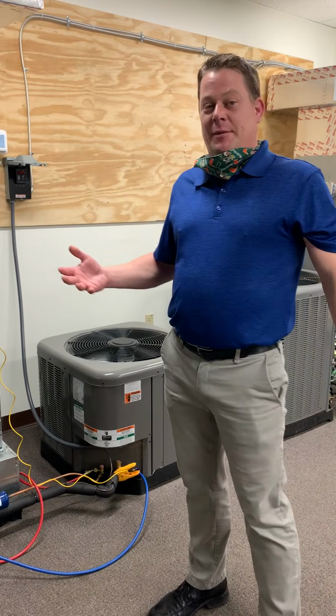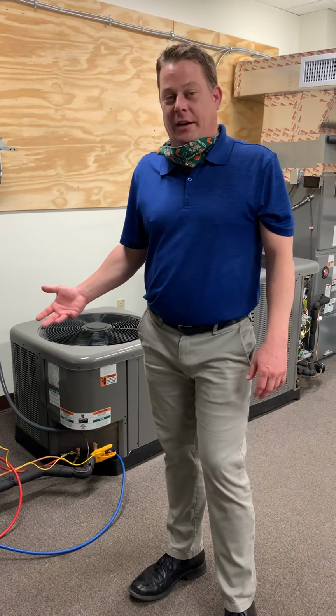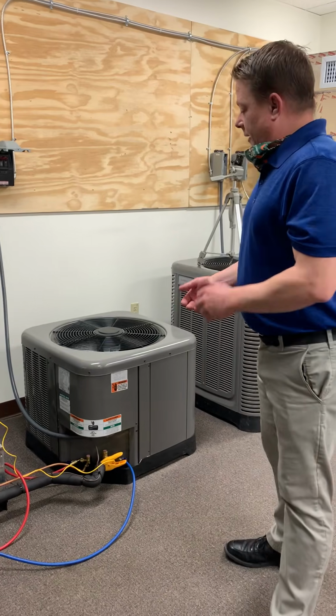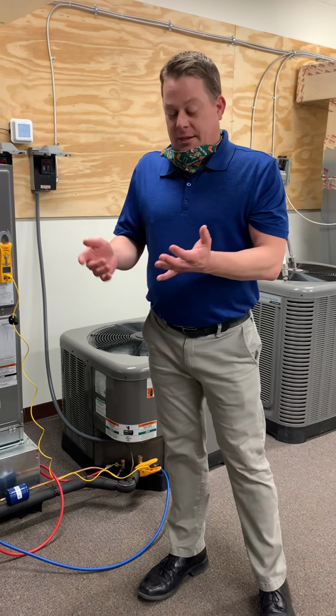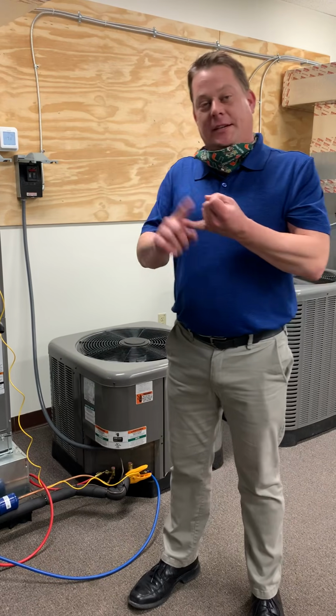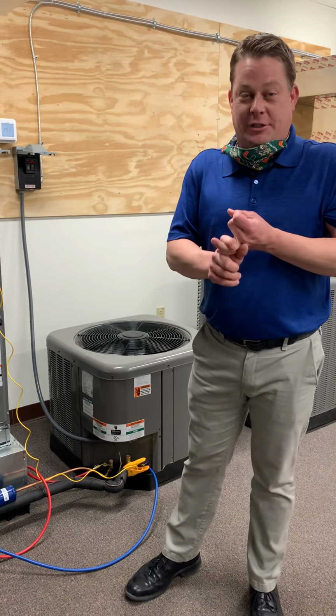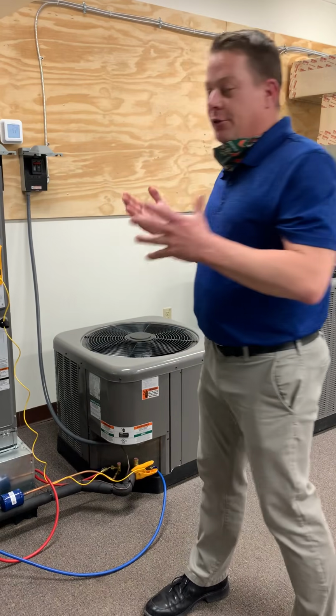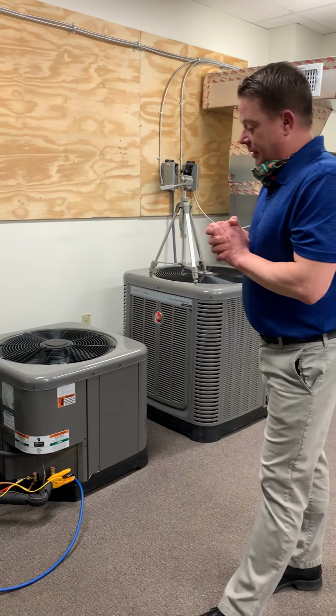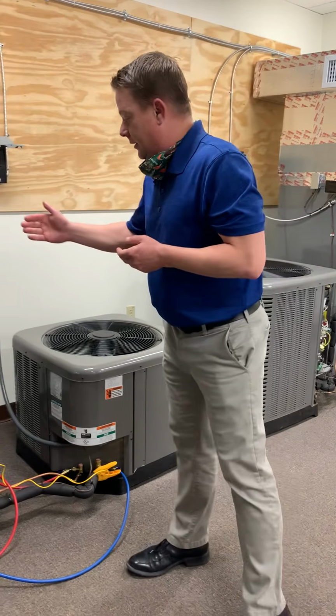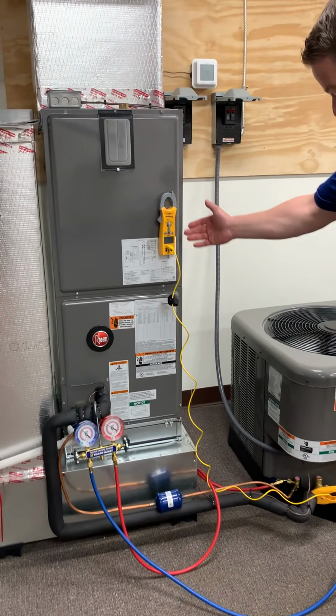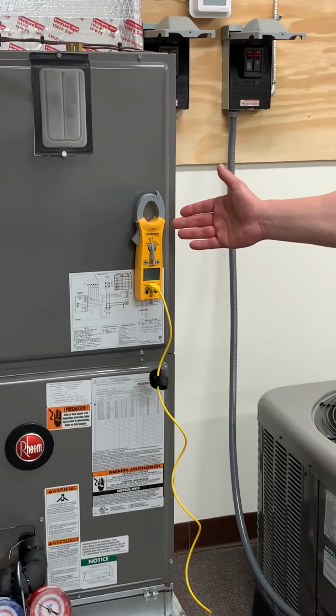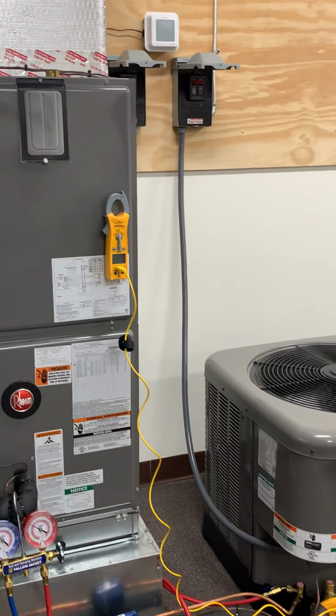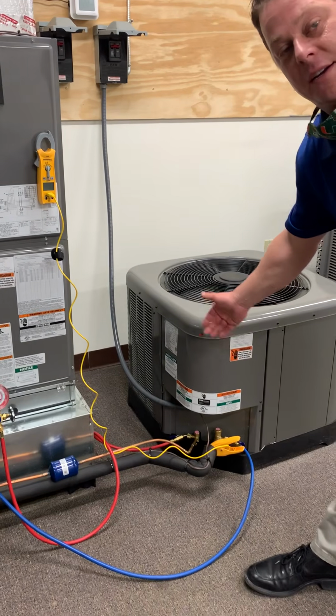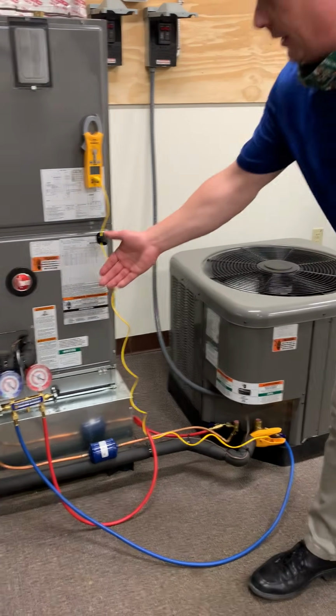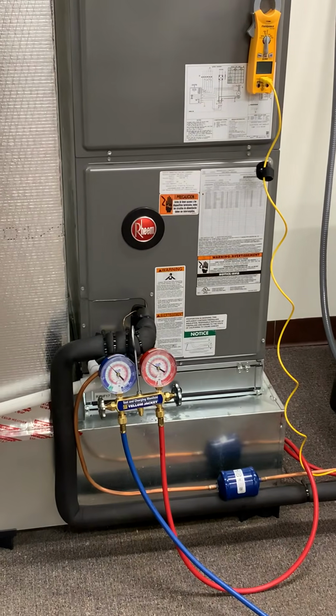In this video, I'm going to demonstrate how to measure superheat and subcooling on an air conditioning system. And why is superheat and subcooling important? It's important in being able to troubleshoot the system and verifying that our refrigerant charge is correct. The two tools that are needed to measure superheat and subcooling are a thermometer, some type of clamp-on temperature reading device, because we need to measure the line temperatures of both our suction line and liquid line, and obviously our refrigerant gauges.